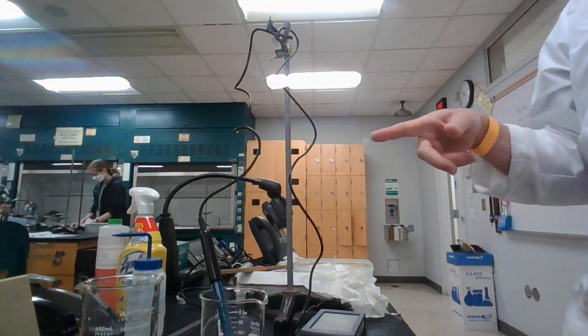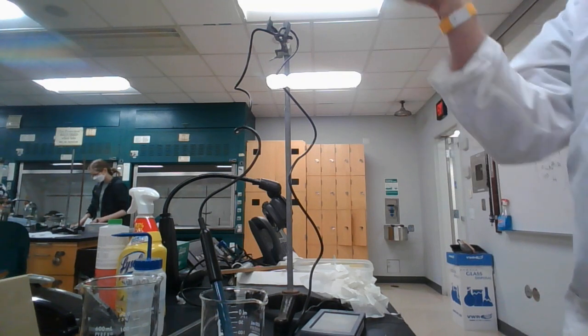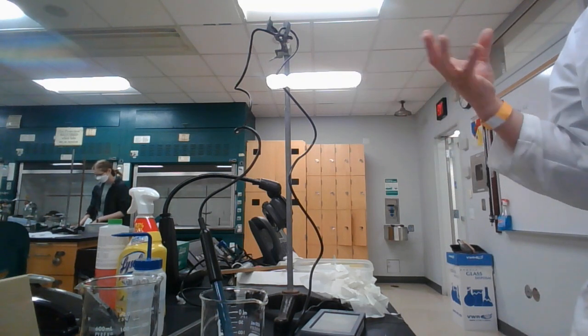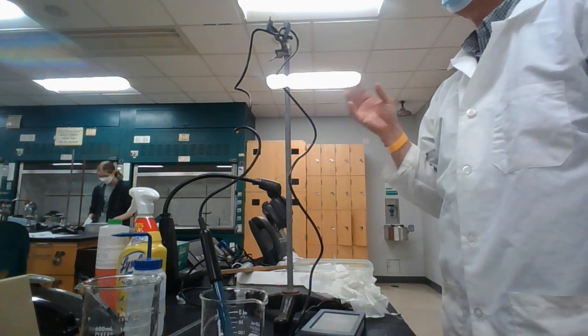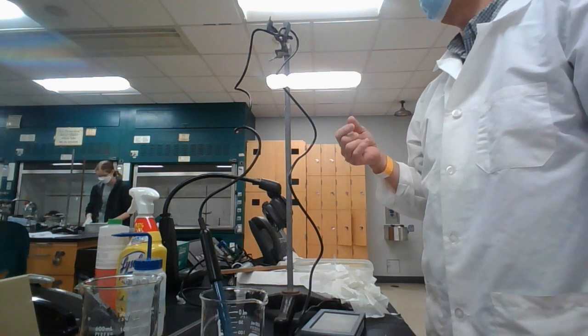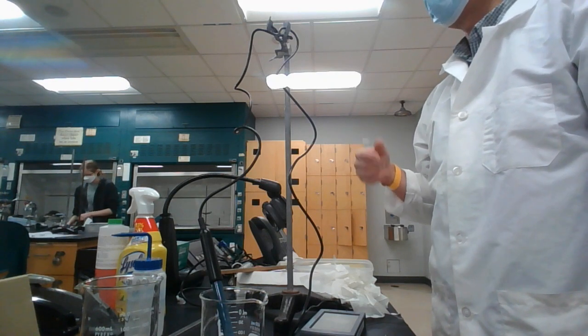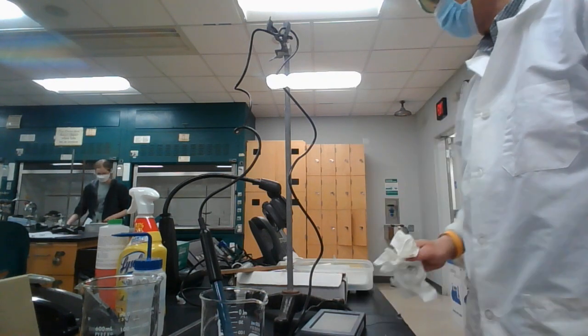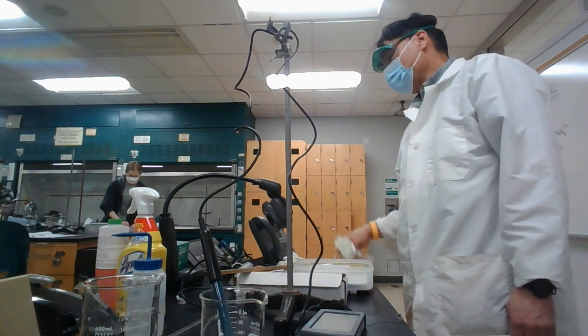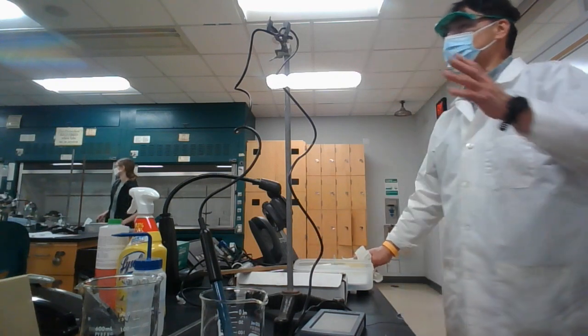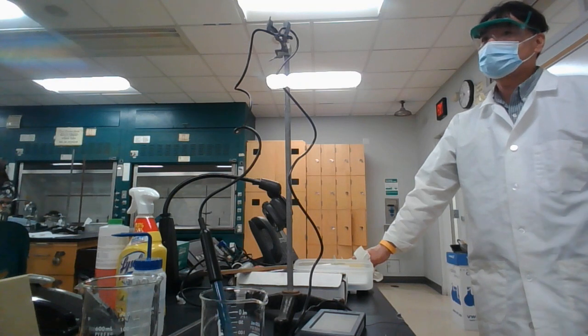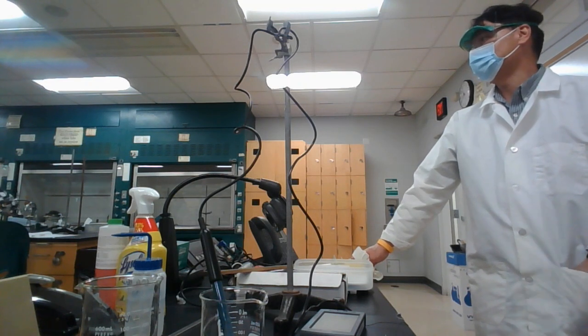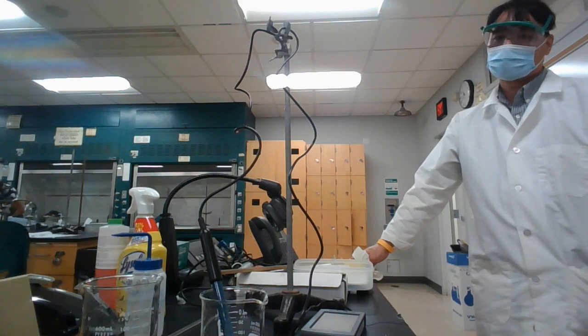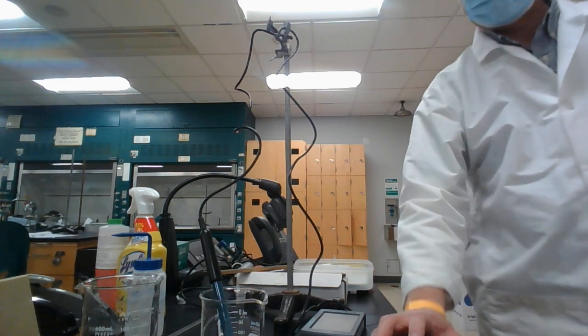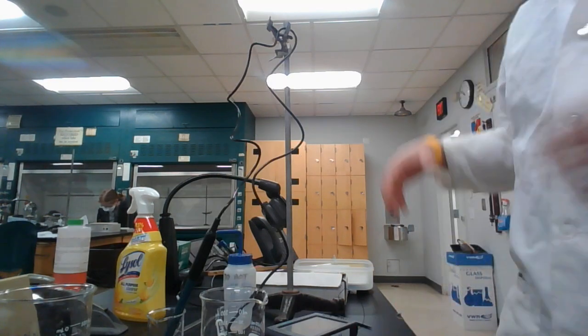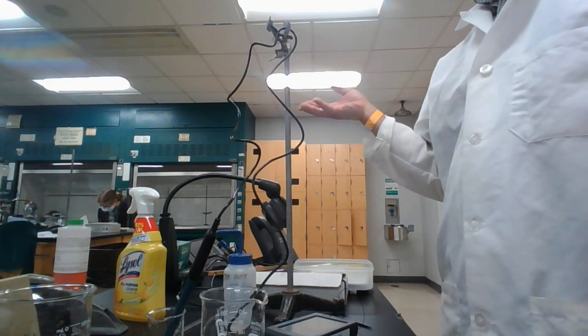One thing you never want to do is let the bulb dry out too much. If the glass bulb dries out, the pH meter becomes very unresponsive. And it's not good because it takes time to condition the bulb. You can leave it in air for a little bit, but not for too long. You always want to leave it submerged in some liquid. Okay, the calibration should last the whole lab period.